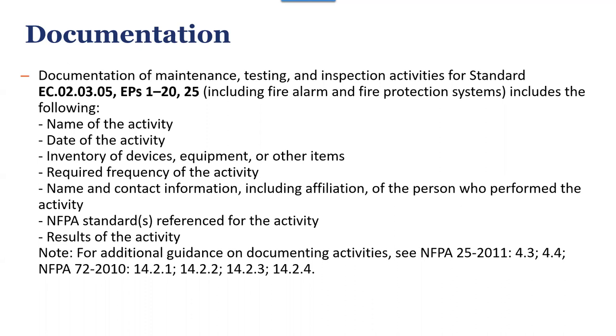The number one thing that's sometimes missing is that the NFPA standards are there, but they're the wrong years. Often organizations are required to show their local AHJ—maybe OSHPD or the local fire marshal—a more current NFPA 25 testing document, whereas for the Joint Commission and CMS, ours is based on the 2012 Life Safety Code and its reference codes.